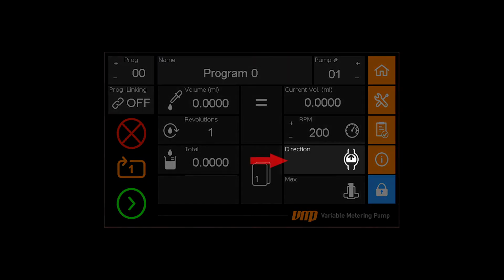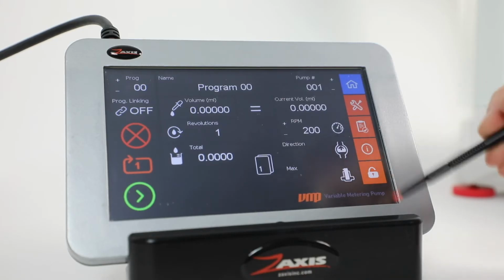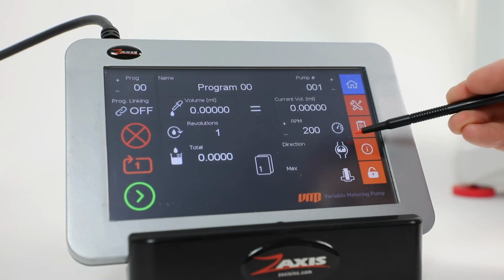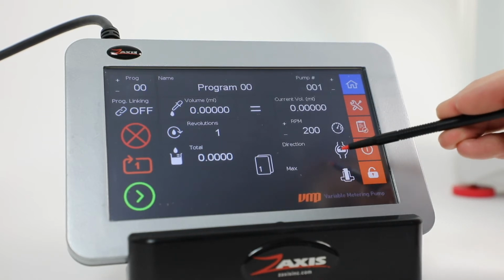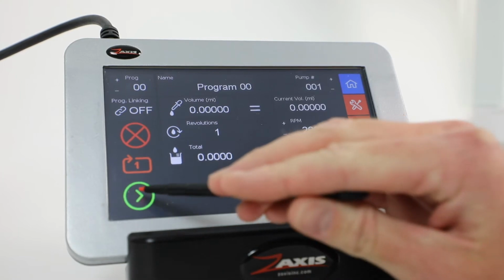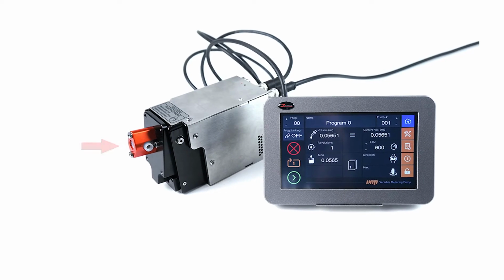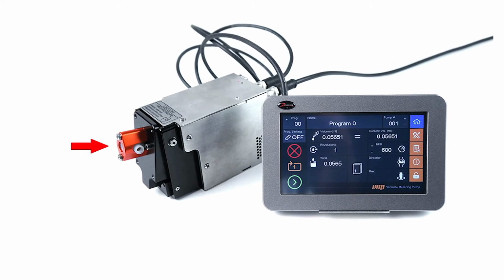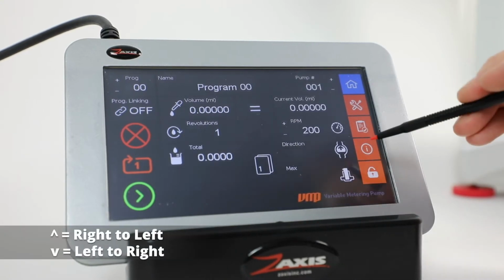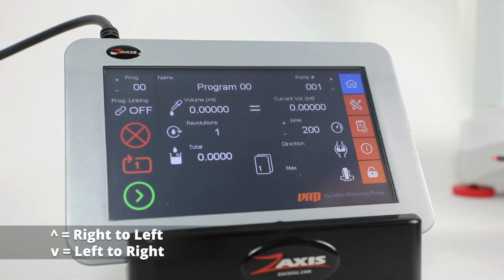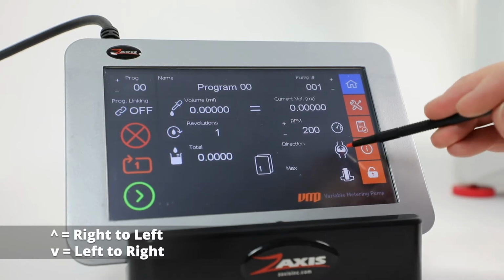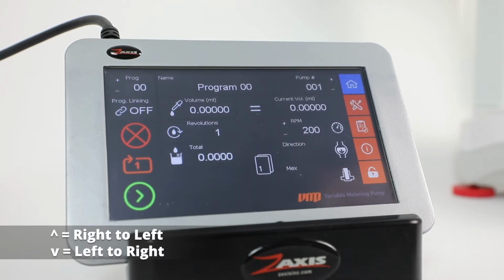The direction here will determine which way the fluid is flowing through the pump head. Currently it's set to pump from bottom to top, as you can see by the arrow indicating here. You can also set it to run top to bottom. If you have a micro pump that has a horizontal port on it, the up arrow will indicate that it's pumping from right to left. If it's pointing down, it will pump from left to right.